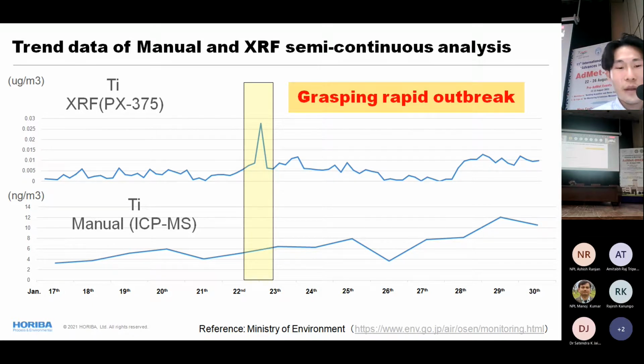As you're seeing, ICP-MS is a 1 day average, and for PX, for this case, it is a three-hour average. And you can see the outbreak of titanium at a particular time, but it's not seen in the manual analysis measurement data.